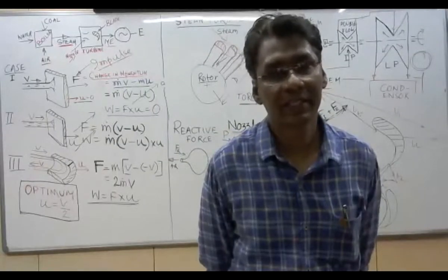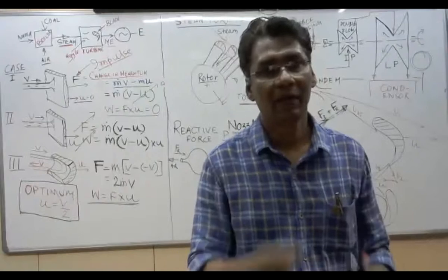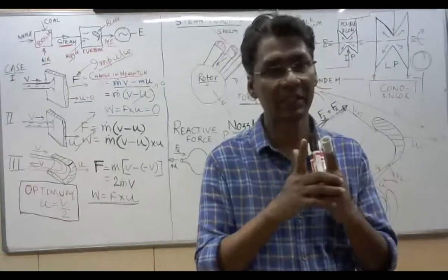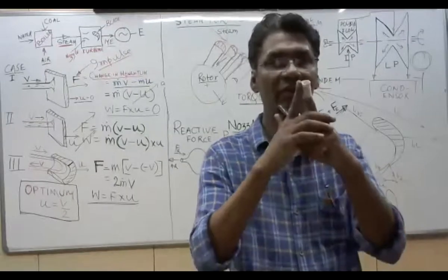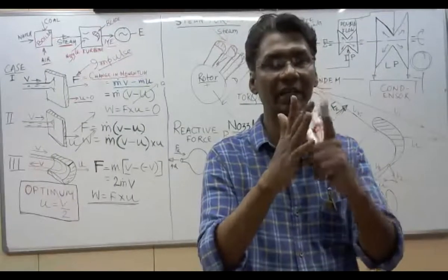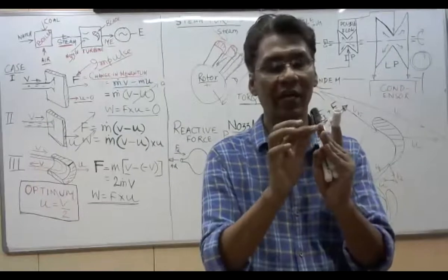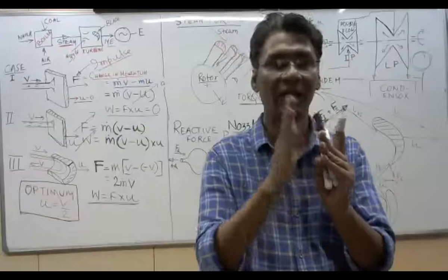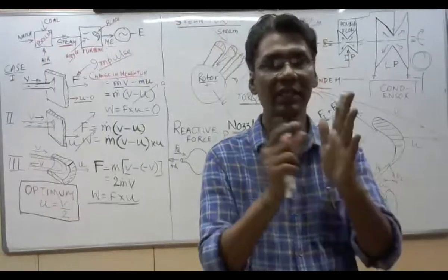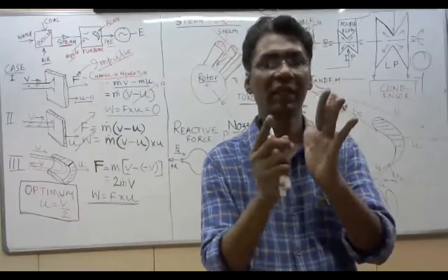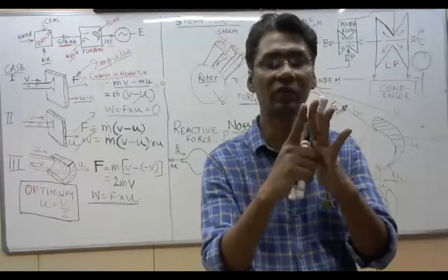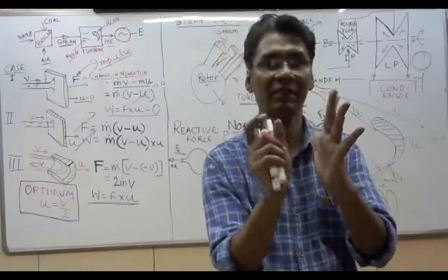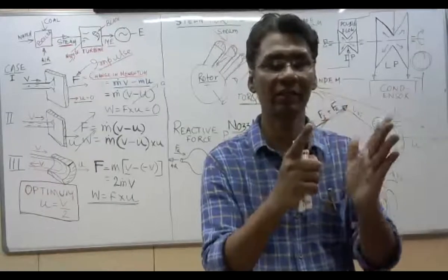There is a blade and a casing. The smaller the casing gap, the higher the efficiency. If we minimize the gap between the moving blade and the casing blade, the carryover loss will be minimum. But there is a restriction, because if there is axial movement of the shaft, it may foul with the stator blades. So it depends upon the allowable limit of axial shift, the clearance between the moving blade and the fixed blade.